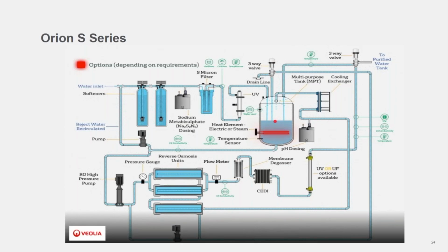This recovery RO will reduce water to drain during the service run by 50%. So if we assume during those 16 hours you're running to service, you won't be throwing away as much water as you would have done previously. It'd be reduced by half. So again, saving on the water footprint. And also, as you can see, on the RO concentrate line, we have an RO concentrate recovery, which recovers some of the energy which we feed back in front of the RO. So there's an RO concentrate pump right at the bottom there.